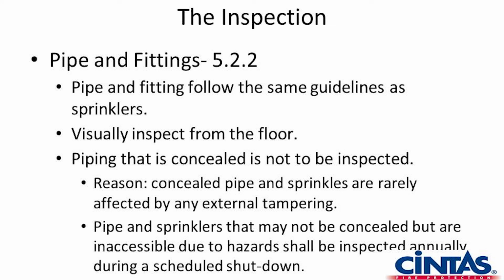We're doing a visual inspection for all pipe and fittings. Again, we're looking at that from the floor. Piping that is concealed is not to be inspected. Again, doesn't mean that we can't, but if it's concealed behind sheetrock, the standards are not requiring us to cut sheetrock out or cut peepholes or anything like that to look at the concealed piping. But any piping that is exposed, we should be looking at that.